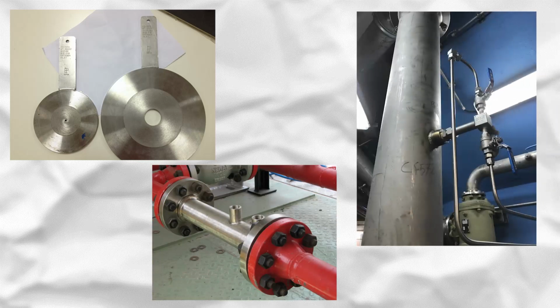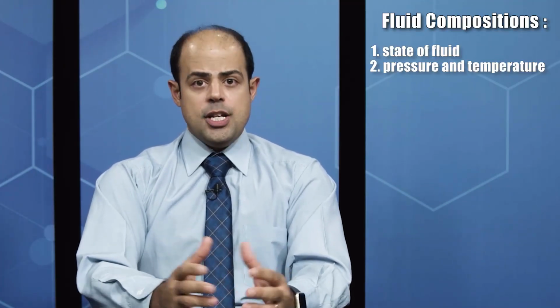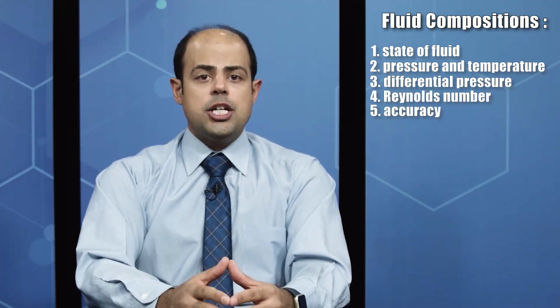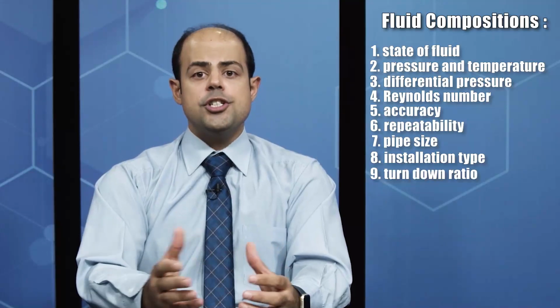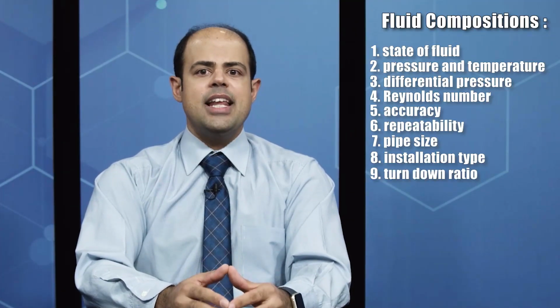Undoubtedly, flow measuring principles could be a little bit complicated, and you might spend enough time dealing with the different types of measuring devices. There are more than 50 methods to measure flow based on differential pressure, velocity, or even mass. The simplest and most typical form of flow measuring is based on differential pressure. To do so, we utilize an orifice plate, venturi tube, or even pitot tube. This principle has less accuracy, but it is cheap. There are a lot of factors which you need to take into consideration to choose a suitable flow meter. I can say the fluid composition, state of fluid, pressure and temperature, differential pressure, Reynolds number, accuracy, repeatability, pipe size, installation type, turn-down ratio, and so forth would have a direct relationship to selecting the best flow meter.